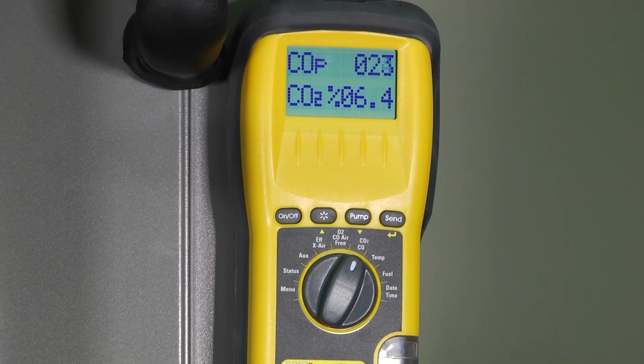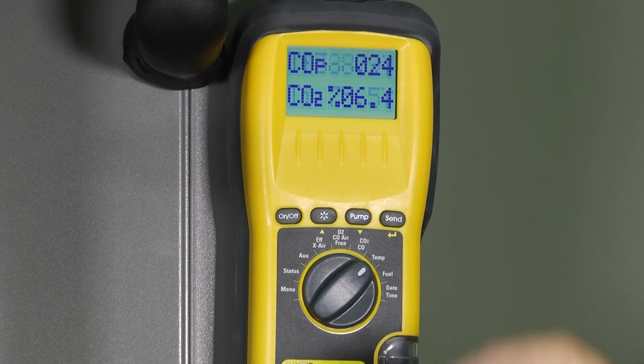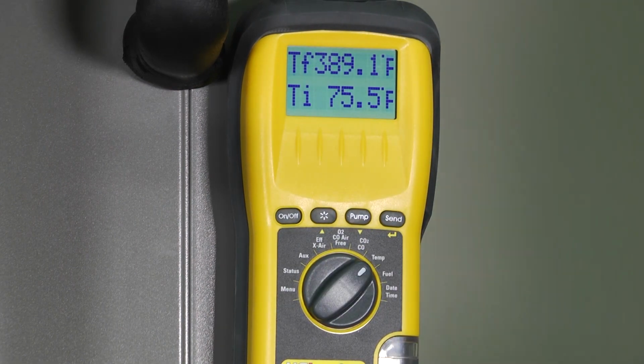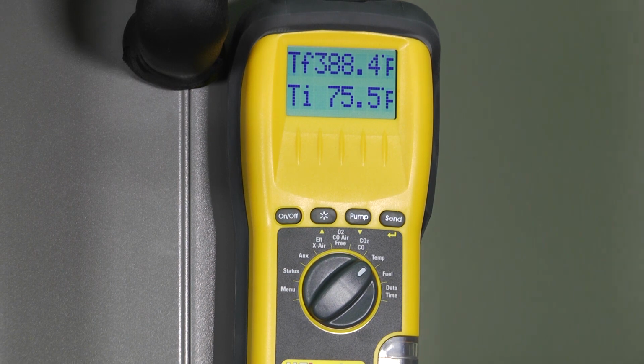The great thing about it as well is I can look at my temperatures, and as you can see here, we're up to 389, 390. I say to myself, but Mark, if I was overfired, I would see that. Well, if all of a sudden I saw a higher temperature reading, I would know I've got a problem. Something as simple as an overfiring of the gas valve can cause way too high a temperature. But I mentioned earlier that we have carbon inside the heat exchanger. That carbon will act as an insulator.